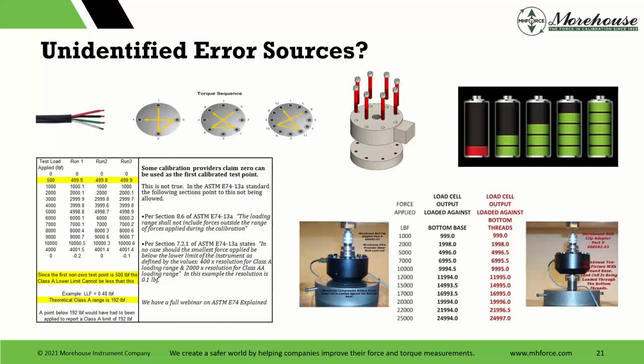Another error source might be batteries. Somebody sends you stuff in with a low charge. The meters might not be regulated, and you might get a different output than if you used fresh batteries. So in our lab, we have Amazon Subscribe and Save. We have batteries coming monthly, and we just put new batteries in everything and calibrate them with fresh batteries, because that's more repeatable than saying, I've discharged my battery, and for you to match my cal, you need to be on 80%, likely, because at some point the batteries are going to stop working.